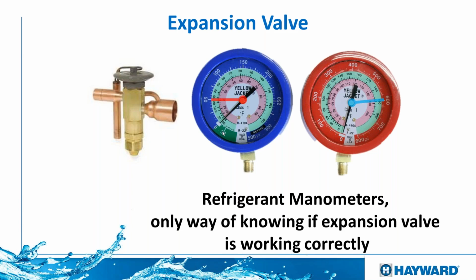Now, today we have expansion valves where you can remove the little head here. You just have to untwist it and then twist the other one back in. We recommend that you bring the pressure of the refrigerant a little bit lower than normal, so it'll be a lot easier to push or install a new one under pressure. And then this little cylinder that you see here, which is attached to the copper tubing of the refrigerant, is just swapped for the old one. So you can do that without doing a lot of welding or soldering with the copper of the unit. So that will be the last one.